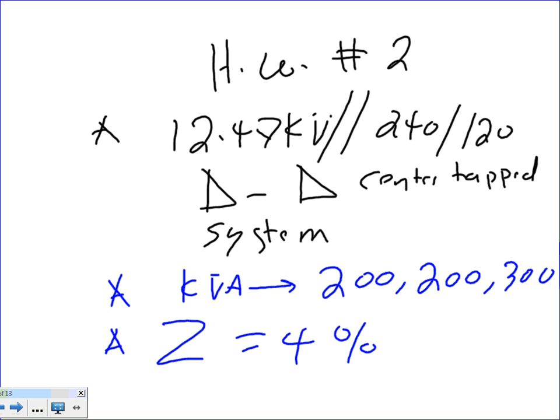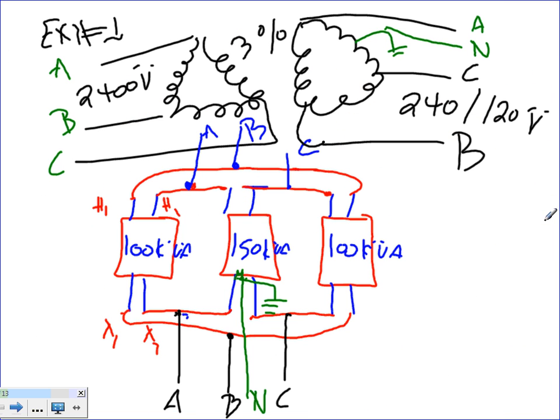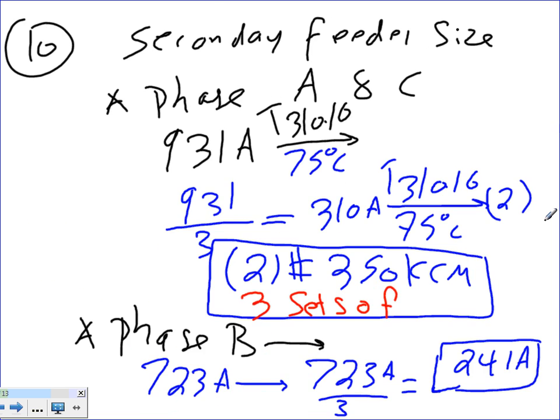So that will give you guys a quick exercise, do the same thing for this homework number 2. Let me just see if we missed anything required here. We gave you the impedance, we gave you the voltage primary and secondary, and almost always the secondary voltage in a system like this is 240/120, almost always. I mean, I've never seen it where it's 480/240. Because what would you use 480/240 for? We don't have receptacles in the US, convenient receptacles, that can run at 240.